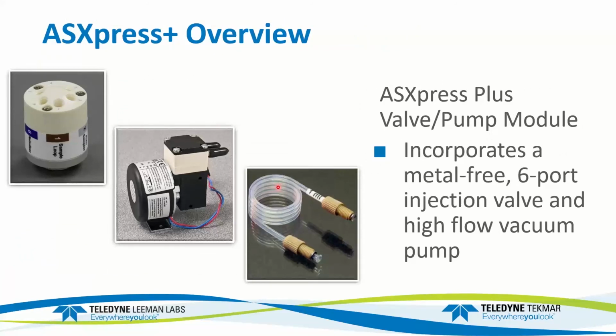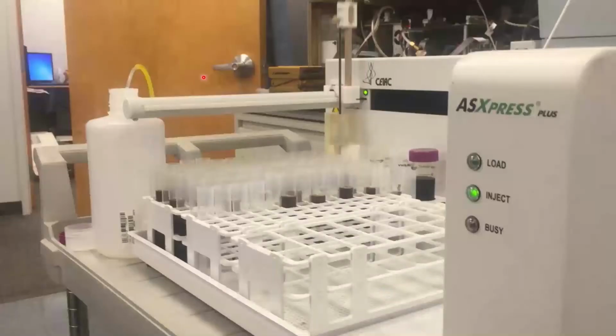So if you look at the ASX Express, and you break it down, here's the 6-port valve system, the peristaltic and vacuum pump, and here's an example of a sample loop right there, and that looks like a 1 mL sample loop, and that's roughly the size of the sample loop that we used in this one. So those are the components of it.